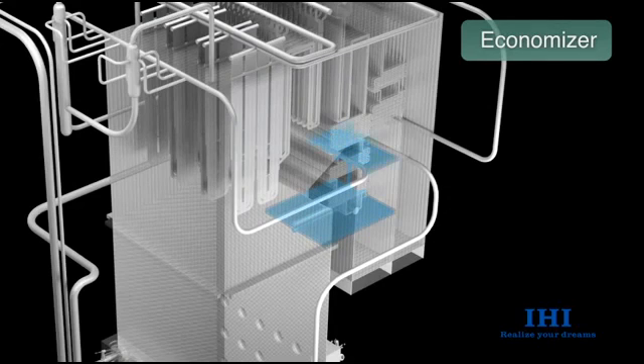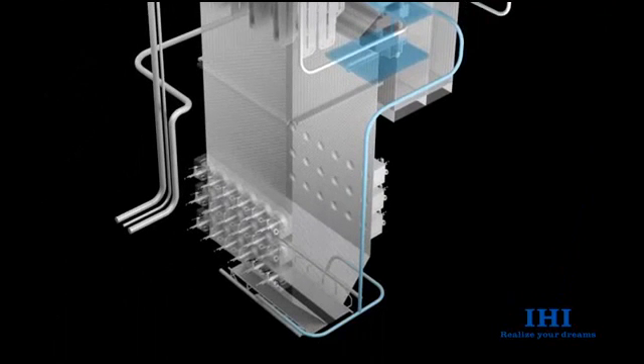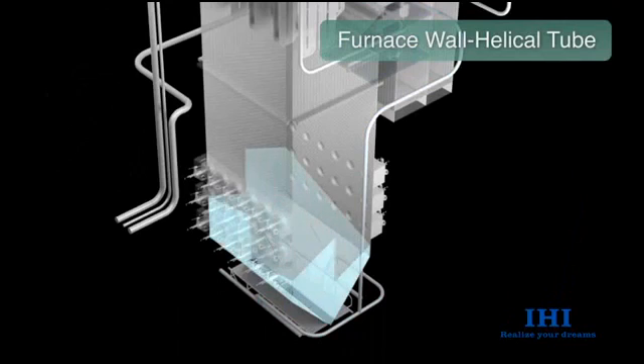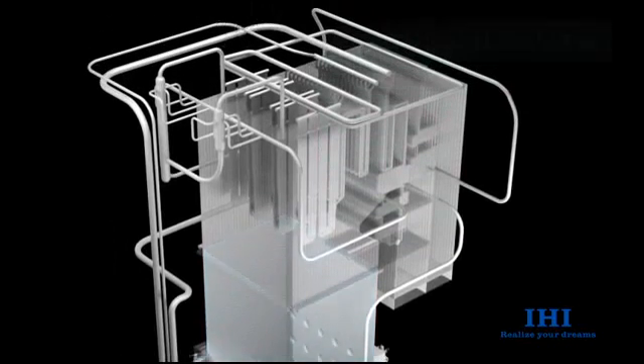The water is fed to the boiler furnace bottom through the connecting pipe and sent to the furnace wall. The water sent into the furnace bottom wall tubes flows uniformly from the lower level of the furnace to the upper level through helical tubes, absorbing the heat from combustion gas. The water converts into steam during this stage and is sent to the steam separators.